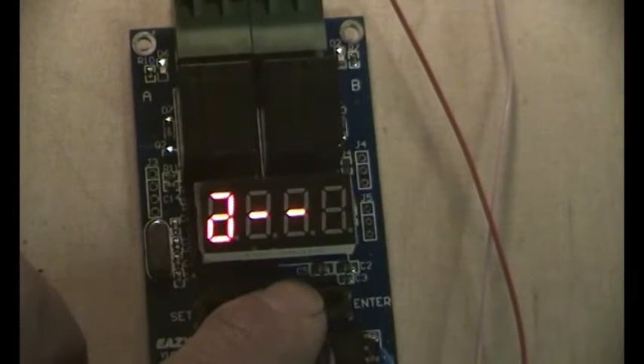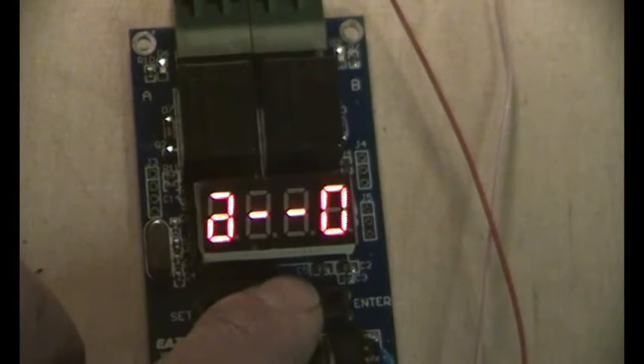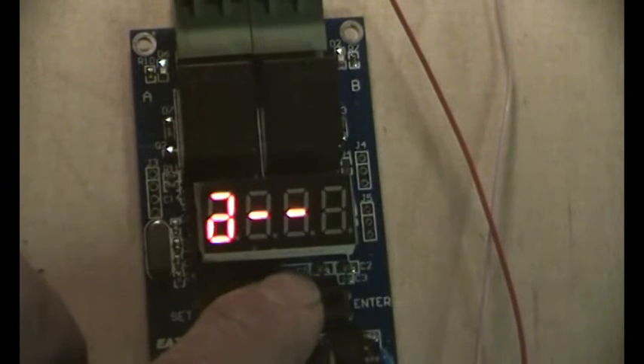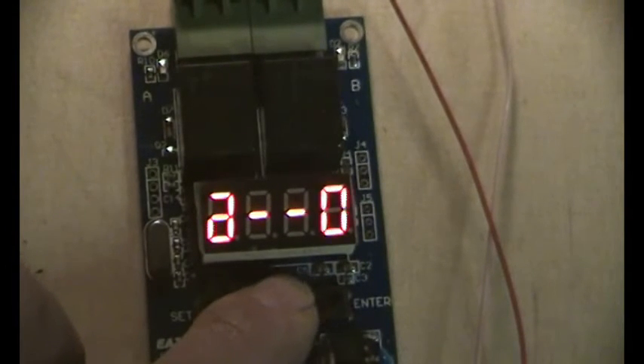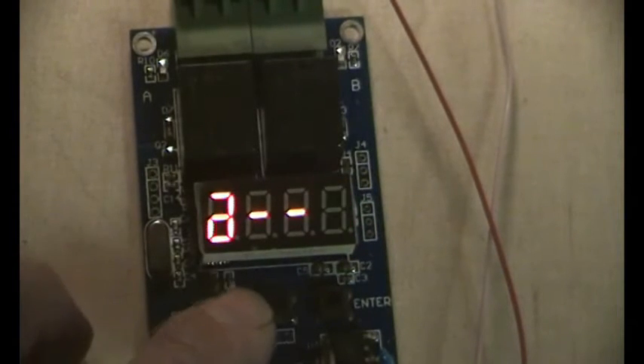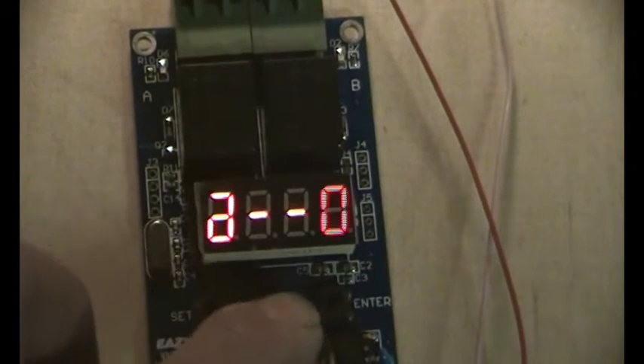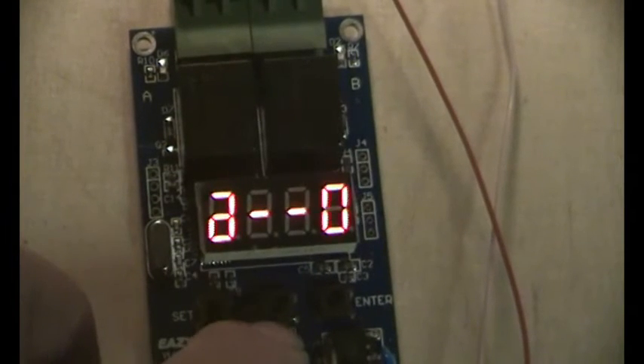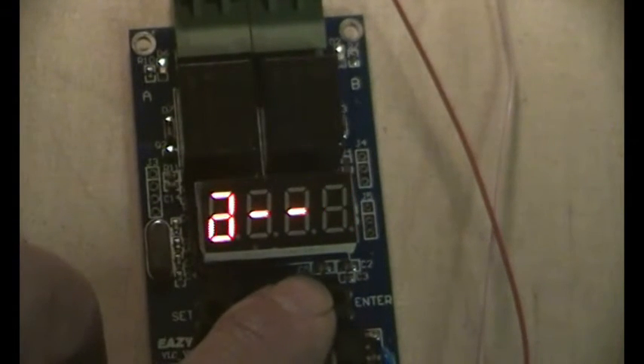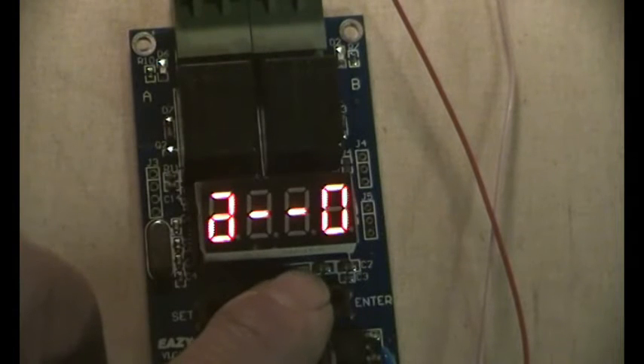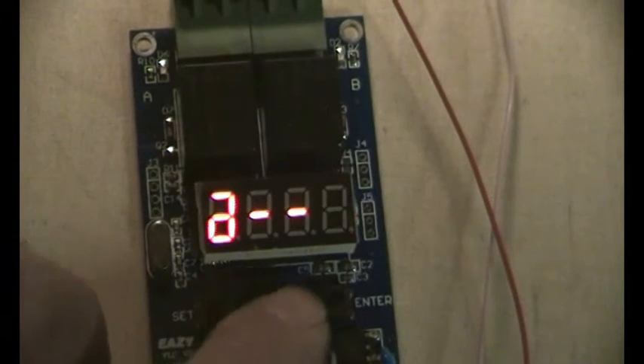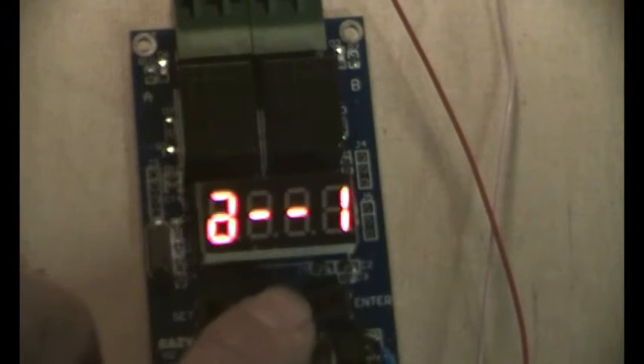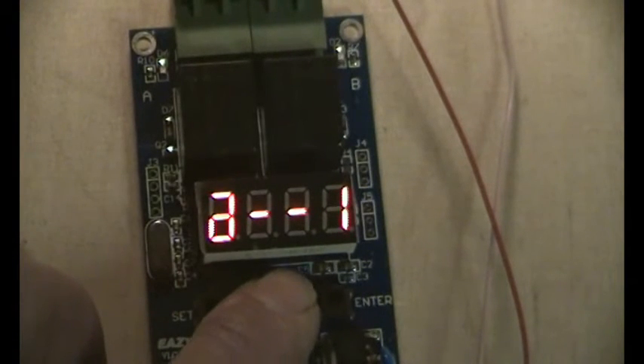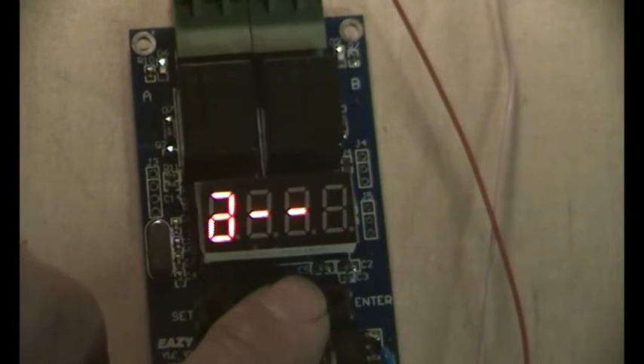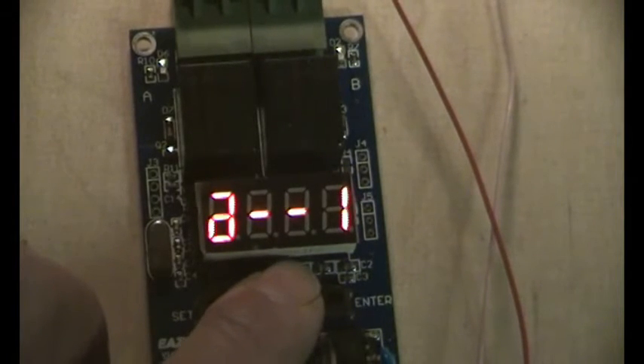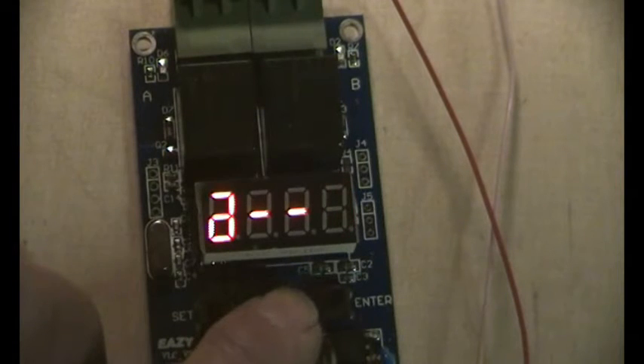But for the system to reset itself, the voltage must go below the low voltage setting. But if you have the two voltages fairly close together, it will just switch off on the voltage setting, and you might get hysteresis, bouncing backwards and forwards between on and off. That's for naught. For one, it swaps the relay action over. So when it was off, it's now on, and when it's on, it's now off.